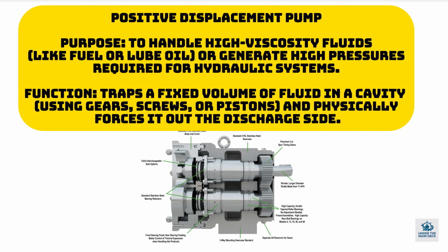Positive displacement pump. Purpose: to handle high viscosity fluids like fuel or lube oil, or generate high pressures required for hydraulic systems. Function: traps a fixed volume of fluid in a cavity using gears, screws, or pistons and physically forces it out the discharge side.